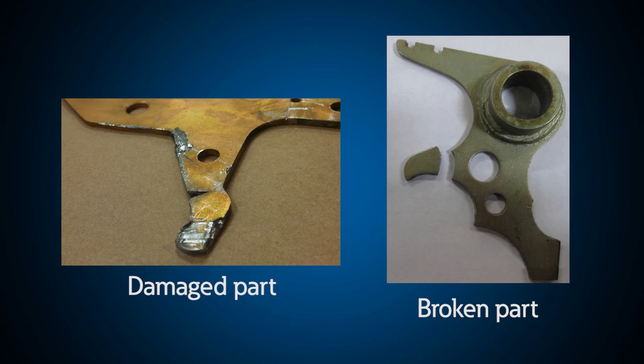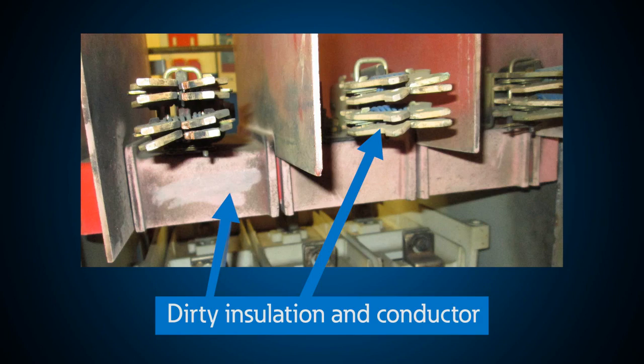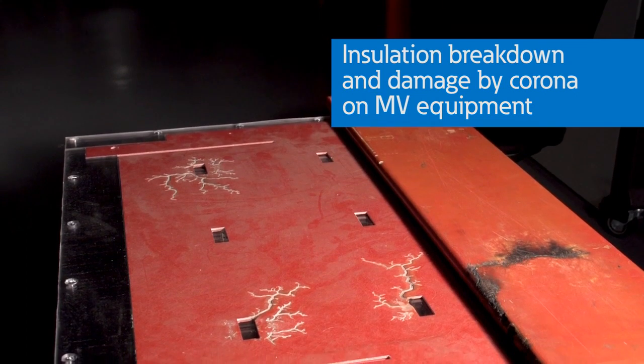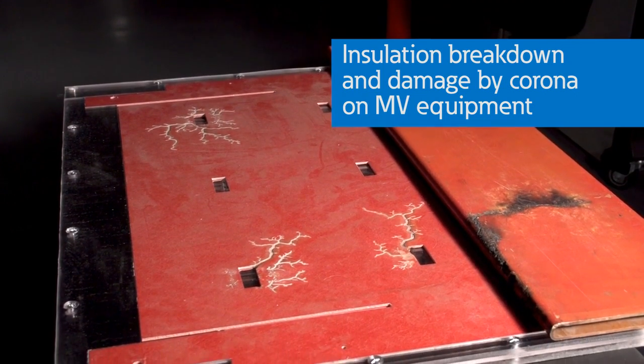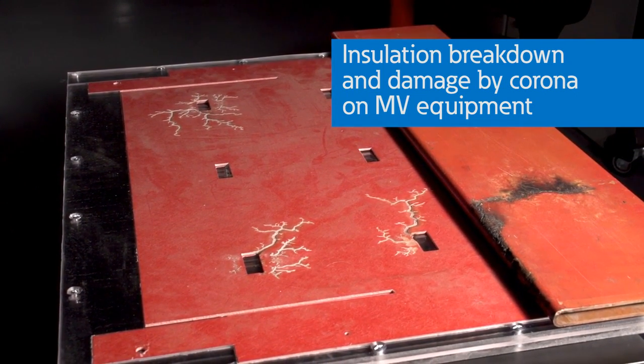Visual inspection of electrical equipment can help prevent possible downtime. Finding a part that is damaged prior to being broken can eliminate what might create an unplanned outage. Simple cleaning of electrical equipment is very important. Some environments may create layers of conductive dust or dirt that can create a major problem for electrical equipment. At medium voltage levels, this can become a path for electricity to flow and create damage to equipment or possibly even an arc flash event.